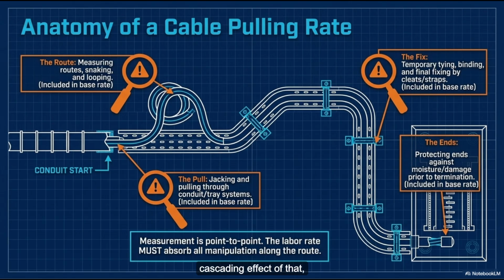Let's talk about the cascading effect of that, because the text goes further into what's hidden in this supply and install rate. It isn't just the copper wire and the tails. The preamble lists out all the required actions, including measuring the routes, snaking and looping the cable, jacking the massive spools, pulling it into the trays, temporary tying, final fixing with cleats, and crucially, protecting the ends against damage and moisture before it's terminated.